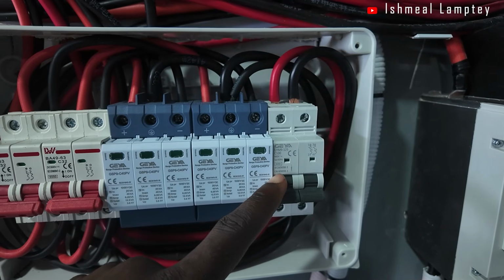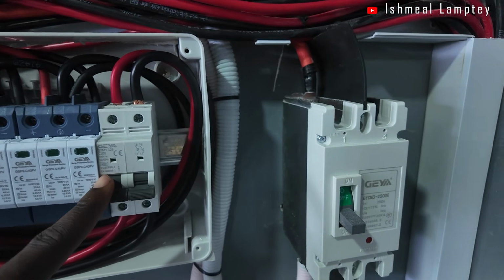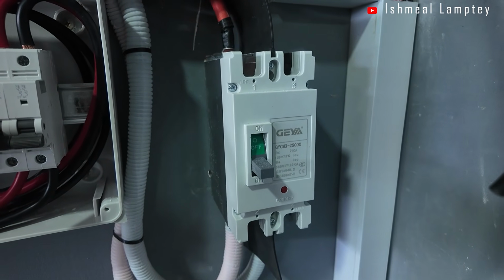So that was what we did. After all that, we fixed our breakers for the battery. Because we're doing 2 different sets of batteries, even though we had 3 batteries, they appeared as 2, because 1 was dedicated to one inverter and 2 dedicated to the other inverter with the help of the breaker box. So we had a DC breaker for that set of batteries, and another DC breaker for the other set, and those were 250 amps each, MCCB type. That's what we used for the batteries.